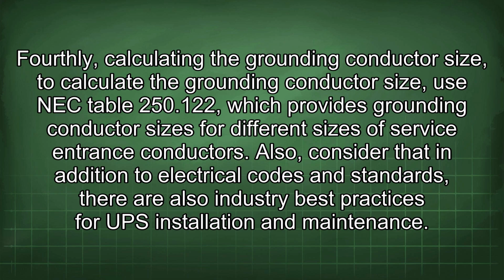Fourthly, calculating the grounding conductor size. To calculate the grounding conductor size, use NEC Table 250.122, which provides grounding conductor sizes for different sizes of service entrance conductors.